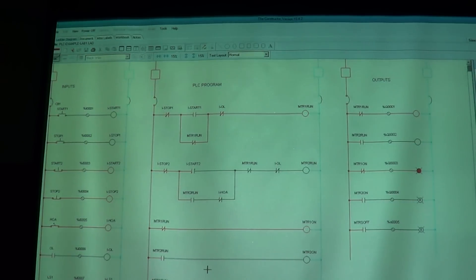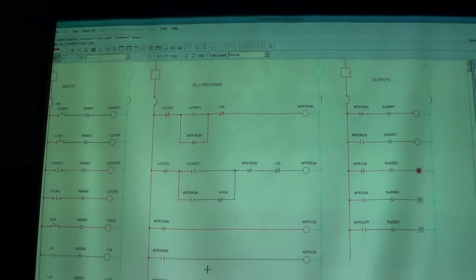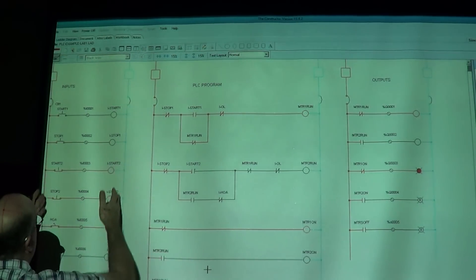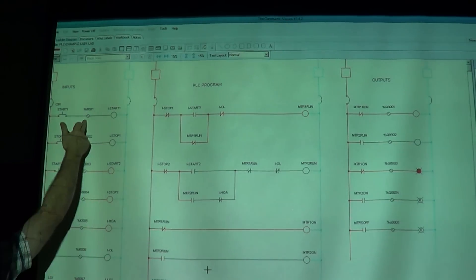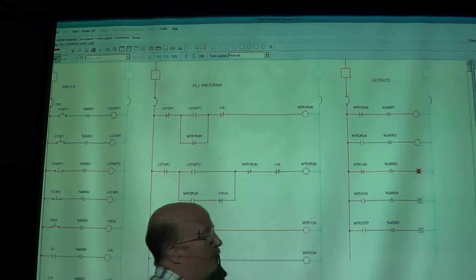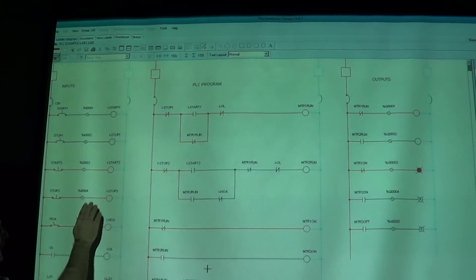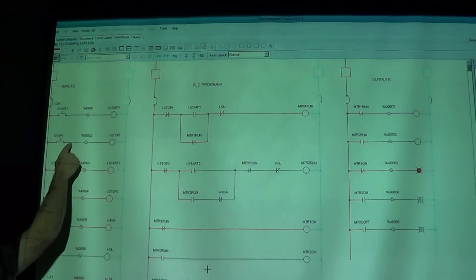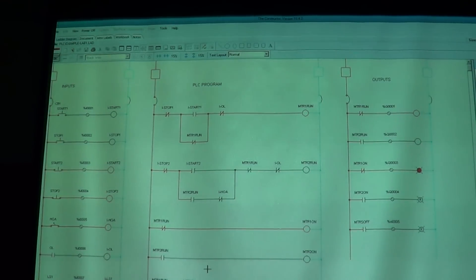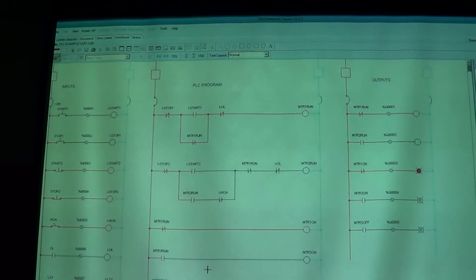What I've got here is a representation we're using — I'll have this file available for you to use. This is a representation of what's outside the PLC and what's inside. You've got three line ladders here. The outside line ladder — here are your contacts, your terminal screws on the outside of the PLC for your inputs. Here are the terminal screws for your outputs, and if you look just inside here you'll see a little relay. So if I connect up my switches, what the switches are doing are energizing and de-energizing relays. Each relay has an unlimited number of normally open and normally closed contacts associated with it.